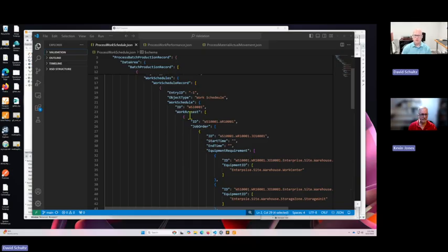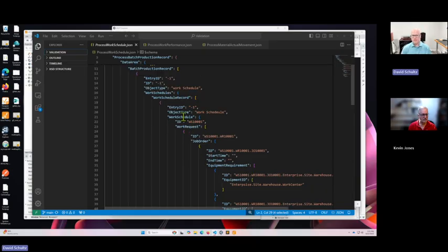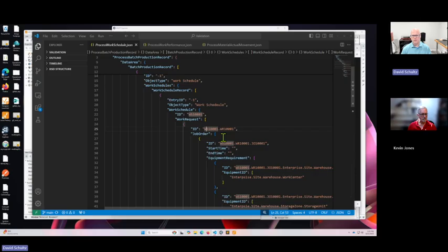Yeah, that helps. So following through, you'll now start to see things that are very familiar to you. This is out of part 4 of the standard. This is all some BatchML type concepts in my work objects. So I have a work schedule. I've given it an ID. That work schedule contains a work request. And the way that I approach this is that I give it a unique ID. Remember, this is the unique ID of this particular event that I'm looking at. So this is the ID of the transaction, if you will. And I like to give as much flexibility because these all need to be unique.